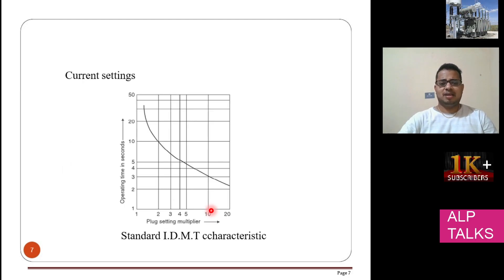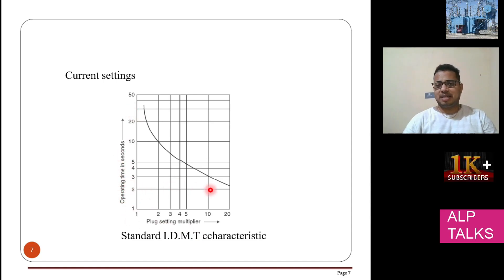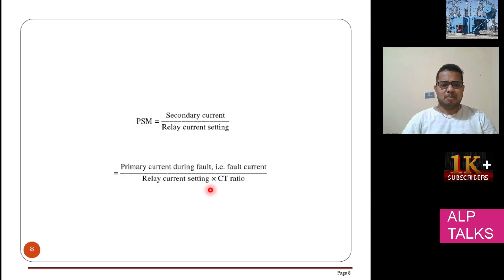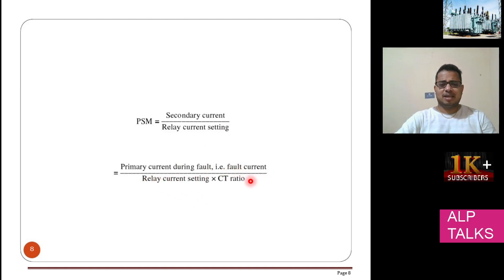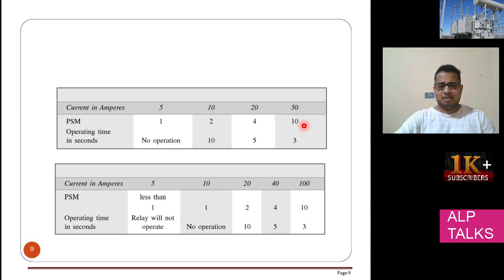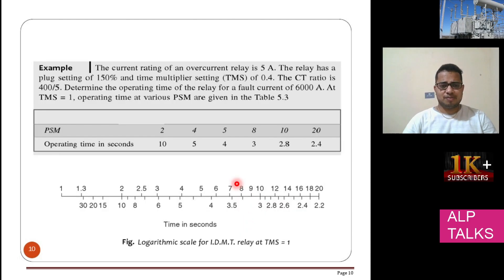There are some current settings — parameters like Plug Setting Multiplier (PSM). The operating time is on the y-axis. In the relay, we have to set the PSM for proper operation. The secondary current divided by the relay current setting gives the PSM. You can set current values such as 5 amp, 10 amp, 20 amp, 50 amp, with different PSM options available. From the graph or table you can see when the relay will operate.